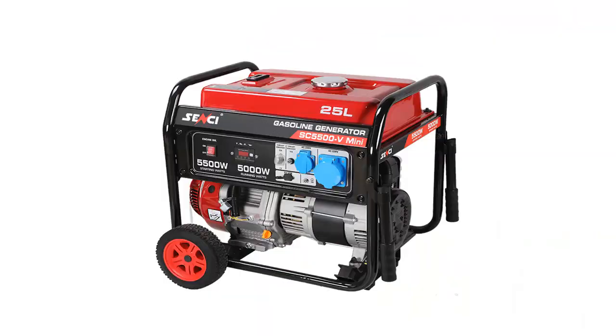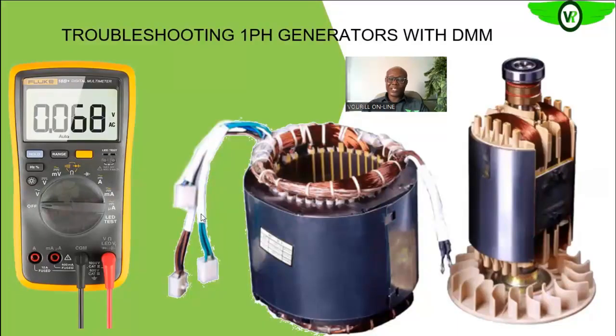So once you have coupled it, connected it to the engine and started it, you can now test on the terminal block for the single phase AC voltage, which is supposed to be 220. If you are not having 220 volts, it means that something is wrong with the entire circuitry. So you can start with the AVR or the diode assembly that is external, outside. You test the diode assembly. If it is bad, you can replace it. Or if it is an AVR, then you replace it. Then on the outside, you also have the terminals from this generator. So you can also test to ground, test for continuity, and then also test if you have that residual voltage on the main armature, which is about 5 volts.